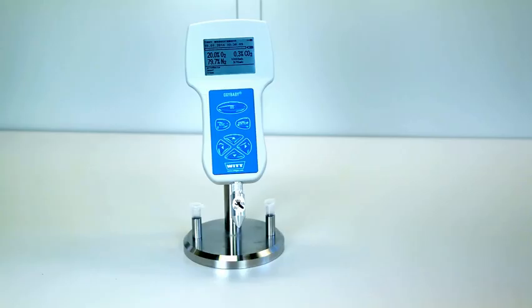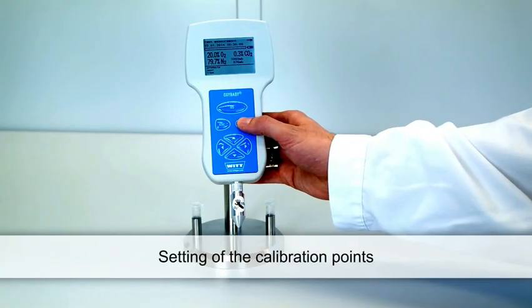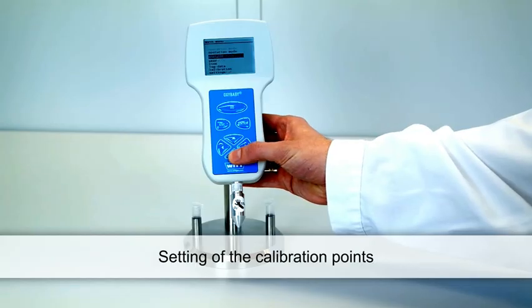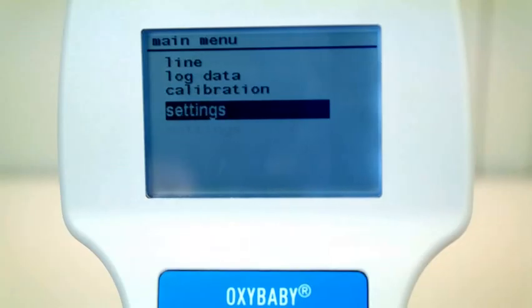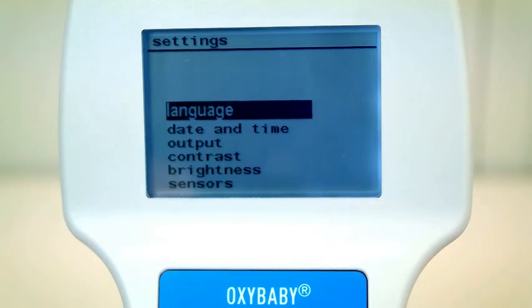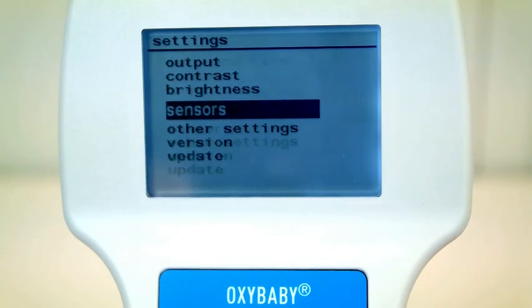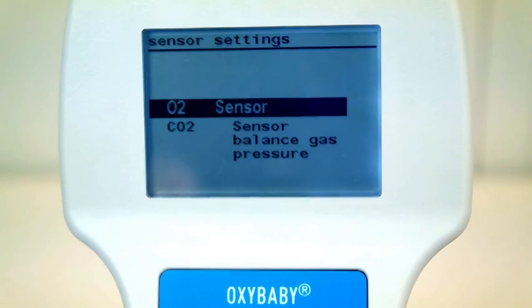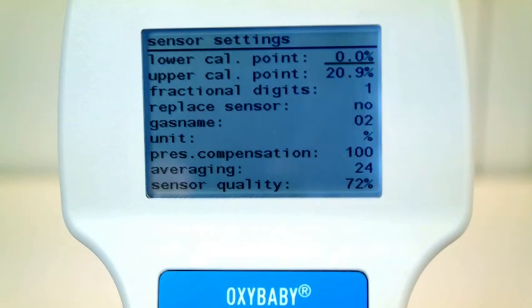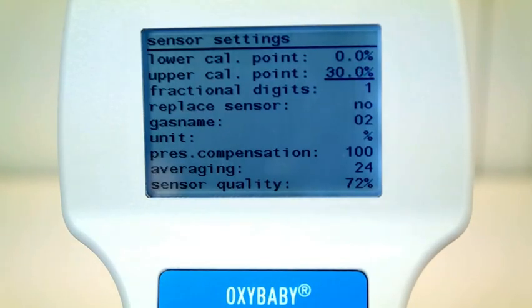The factory provided upper calibration points are 20.9% for oxygen and 100% for CO2. You may modify the calibration points of both sensors to match your calibration gas analysis. Choose the menu item Settings and then Sensors. Choose the sensor you want to set. Now you can fix the calibration points using the arrow keys. Confirm your value with Enter. With the Escape key you can return to the menu item Settings at any time.